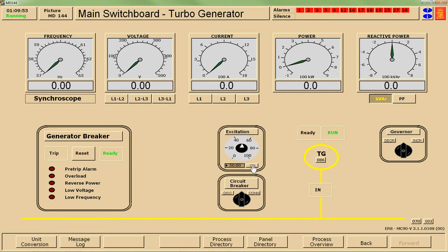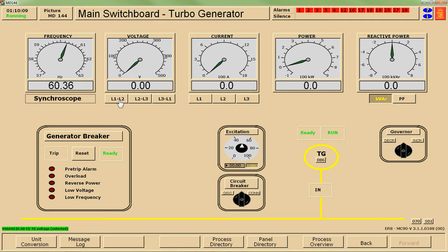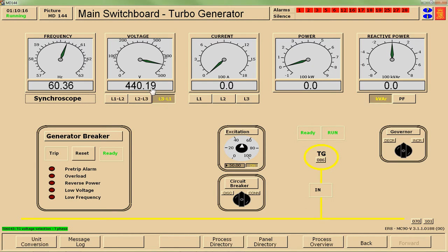The first thing I'm going to do is turn on my excitation. We can see now that we are starting to read some values with our generator. I don't read voltage yet, however, because it's a three-phase system I need to read the voltage across phases. Picking any of those phases gives me my voltage, and I can see that my generator seems to be working.